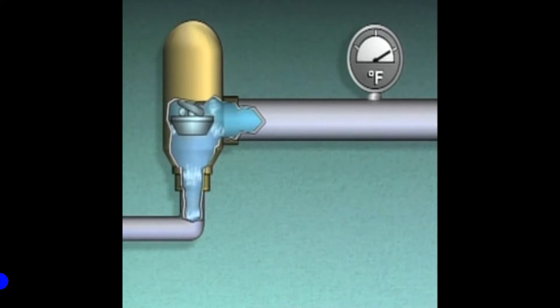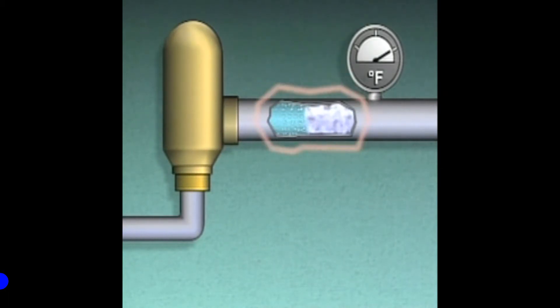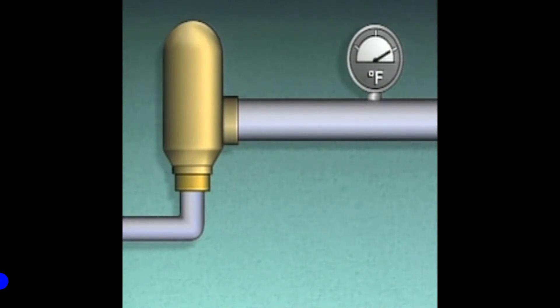This drop in pressure also causes the temperature of the refrigerant to drop. As heat transfers to the refrigerant, the refrigerant begins to boil or vaporize. The refrigerant then flows past the thermometer and absorbs heat from the thermometer and the area around it. The temperature indicated on the thermometer decreases as the liquid refrigerant flows by, absorbs heat, and becomes a vapor.